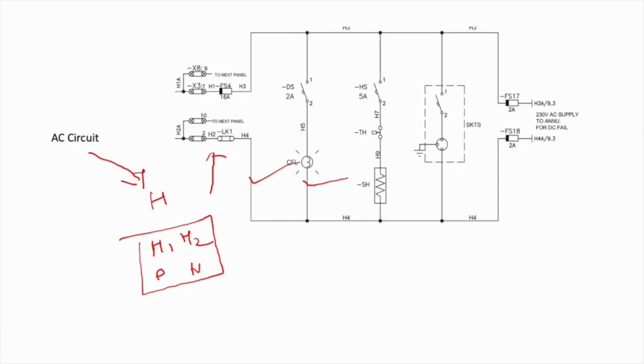We also place a fuse inside each circuit so that if there's a problem with any of the circuits, the fuse will isolate the circuit. Again, this problem won't escalate and cause damage. Every circuit has a fuse. There's no fuse only in CT circuits, because high current flows and the fuse would melt. It's simple.